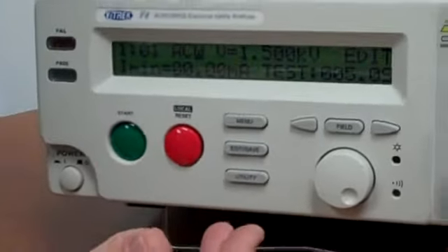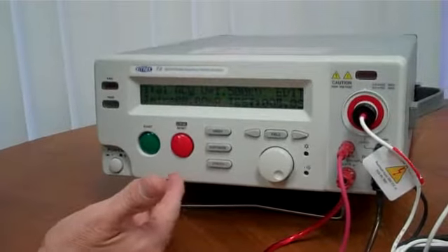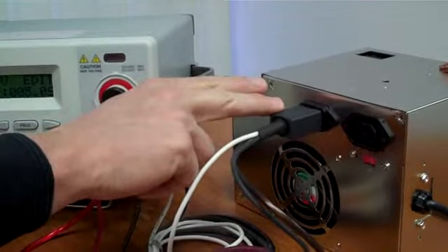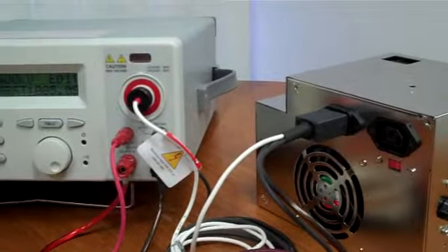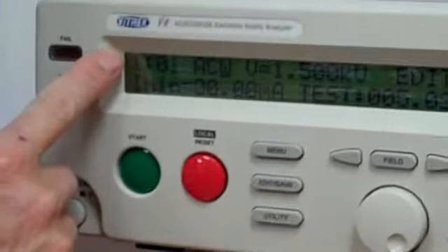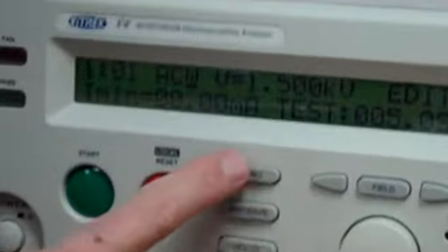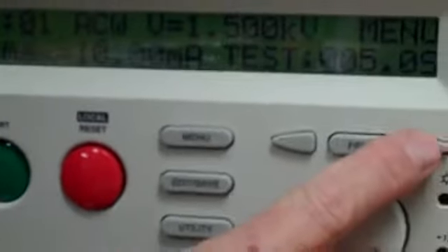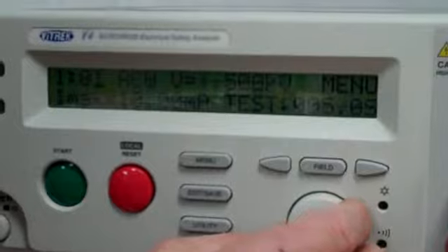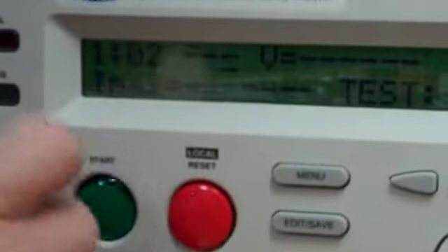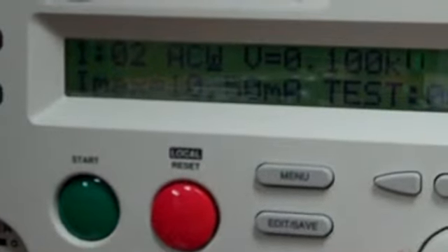Now, if we wanted to add on an additional step, like a ground bond step, to make sure that we have good continuity from our chassis to the earth ground pin on the power input, then we come up to the step number, which is 1.01. We want to change that to 1.02. I'm going to press the menu button, and we're going to cursor over to the unit digit and dial up 1.02.